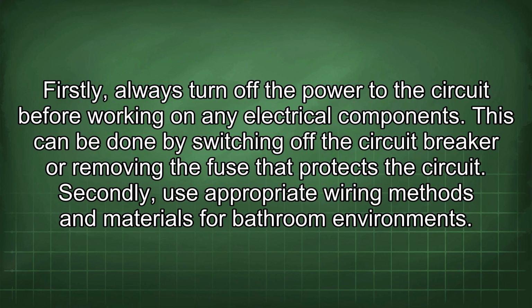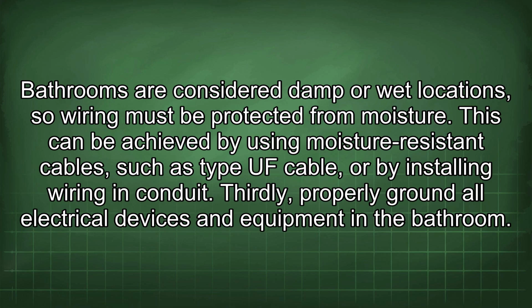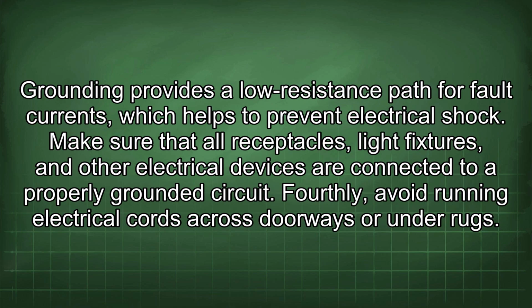Secondly, use appropriate wiring methods and materials for bathroom environments. Bathrooms are considered damp or wet locations, so wiring must be protected from moisture. This can be achieved by using moisture-resistant cables such as Type UF cable or by installing wiring in conduit. Thirdly, properly ground all electrical devices and equipment in the bathroom. Grounding provides a low-resistance path for fault currents, which helps to prevent electrical shock. Make sure that all receptacles, light fixtures, and other electrical devices are connected to a properly grounded circuit.